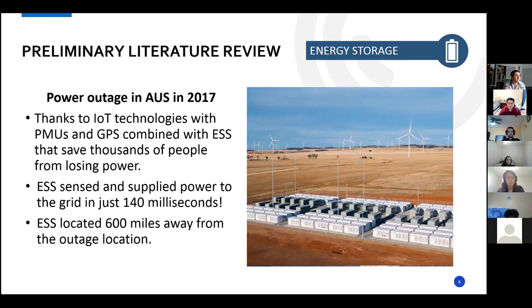More importantly, the energy storage system, located over 600 miles away from the outage location, can sense it and kick in enough power to maintain the grid, at around 7 cycles, which is 0.14 seconds - really fast.